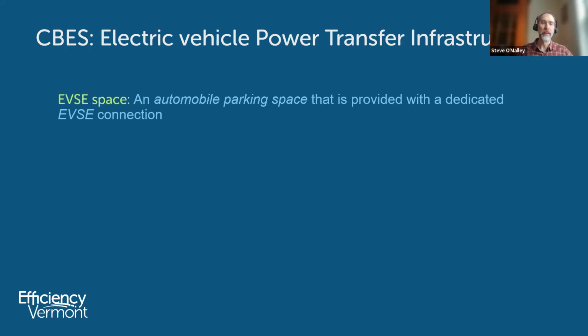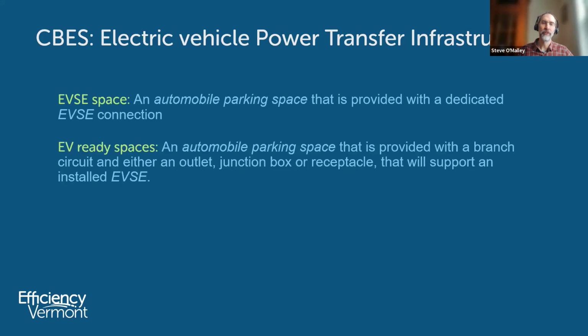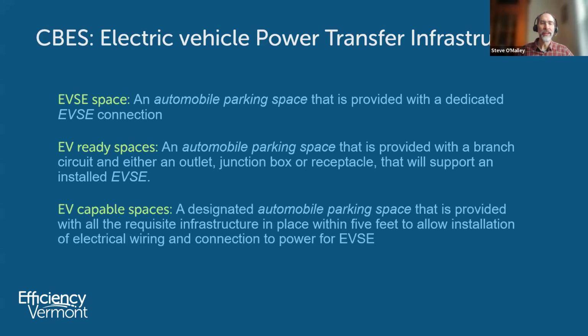Here are some definitions from that table. EVSE: electric vehicle service equipment space, an automobile parking space provided with a dedicated EVSE connection. EV ready space: a parking space provided with a branch circuit and either an outlet, junction box, or receptacle that will support an installed electric vehicle service equipment. And EV capable spaces, which showed up for our group R2 multifamily buildings: all requisite infrastructure is in place within 5 feet to allow a future installation of electric wiring and connection to power for electric vehicle service equipment.